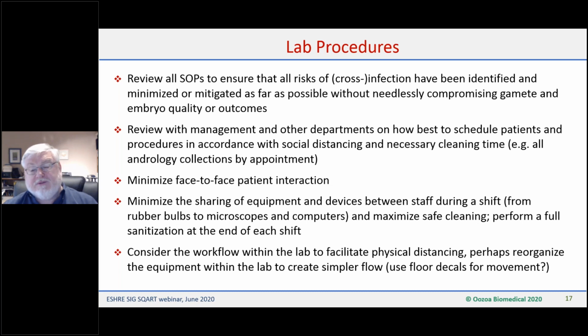And you might even consider using floor decals to get people to move in certain directions so that paths don't cross, or that people are not going to come close to each other when they don't need to, because there's another way that may not be the way they've usually gone, because it's a few paces longer. We've designed labs for 35 years or more now, and what we've always been doing is looking at flow to keep things going in a single direction if possible, minimize paths crossing and that sort of thing.